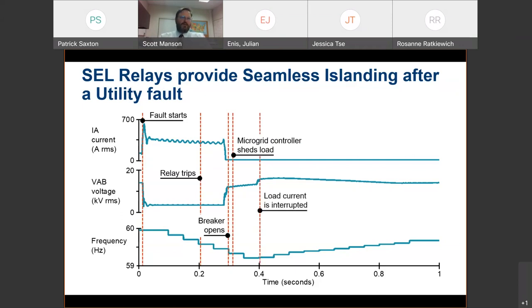So it does so in what's called a load shed. This is losing a finger to save a body. This is saving a power system at the cost of losing some pumps. Small loss for a huge gain for very low cost. In this case, the loads were interrupted, and look, the frequency recovered. It was a real event. This is what multifunction protection relays do for a living. Sadly, most people don't utilize this capability. But now, with inverters, you have to. This is what the future holds. You need intelligence everywhere.